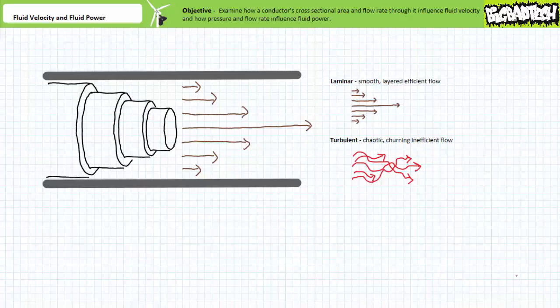Beyond a certain fluid velocity transition point, flow becomes turbulent. Turbulent flow is characterized by a chaotic, churning action and is inefficient — systems experiencing turbulent flow might run unusually hot and exhibit early thermal breakdown of the oil. The velocity at which flow transitions to turbulent is described by the Reynolds number, which depends upon properties of the fluid, specifically velocity and kinematic viscosity — a measure of a liquid's resistance to flow.